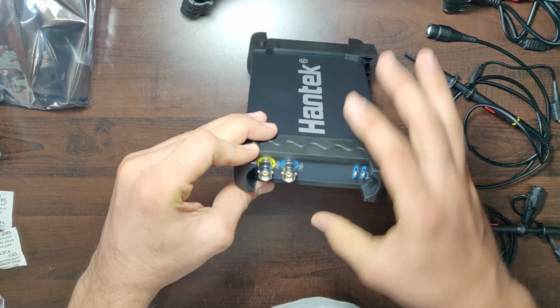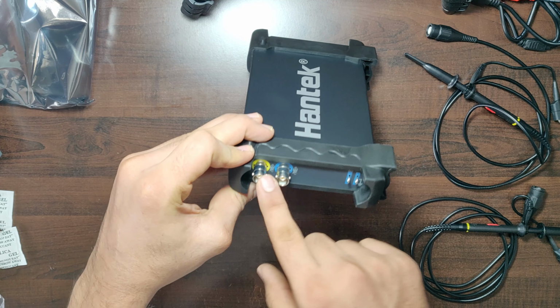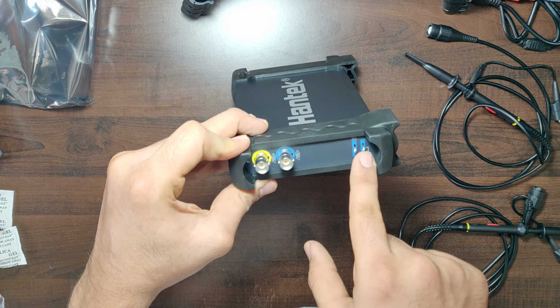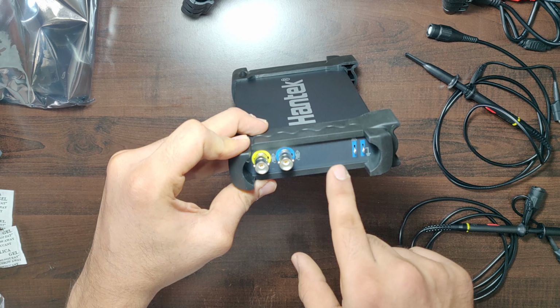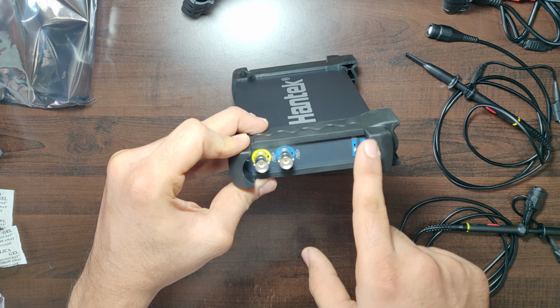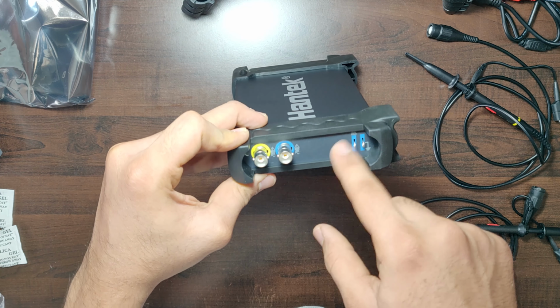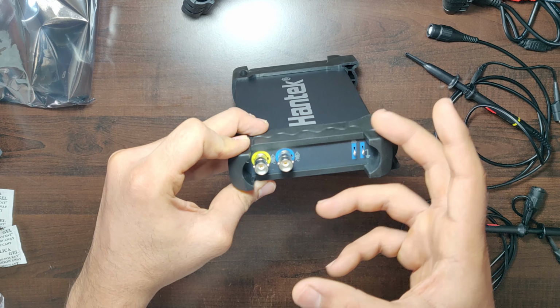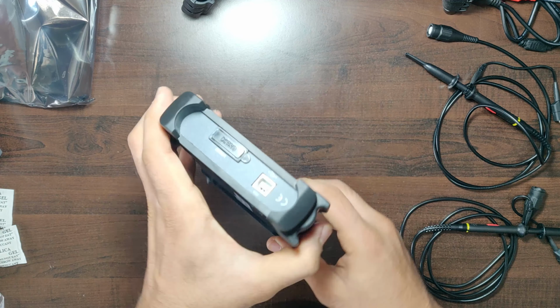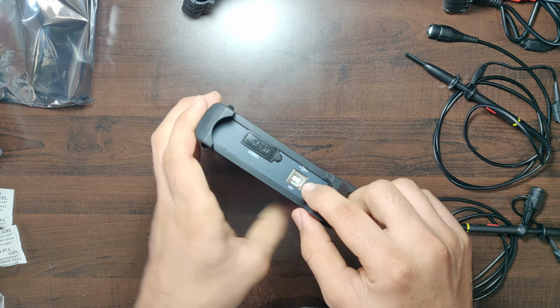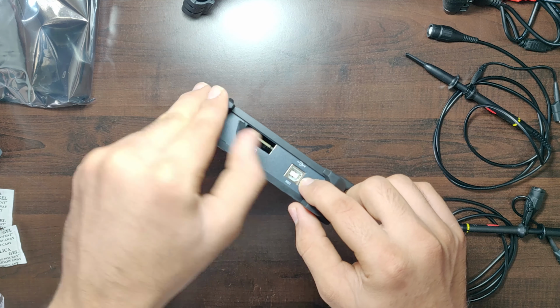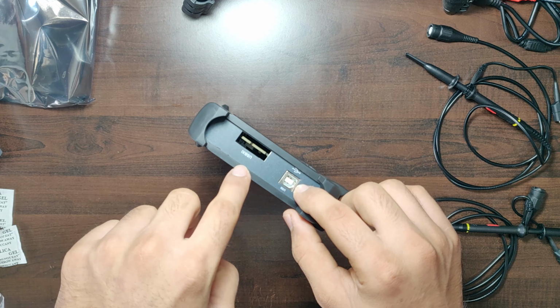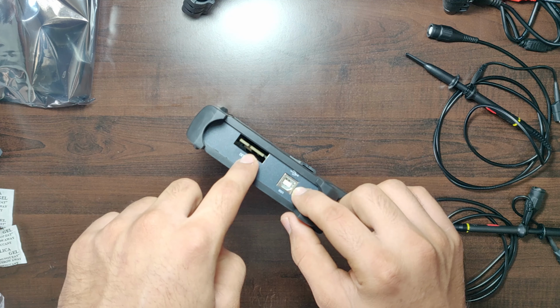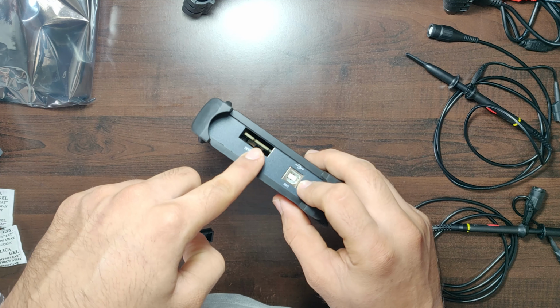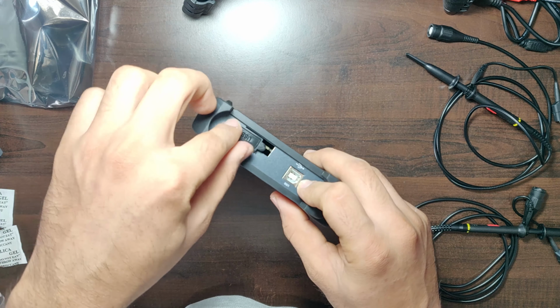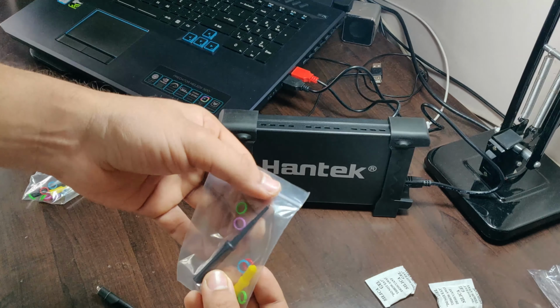Coming into the ports, here you can see the channel 1, channel 2. These are the two ports where you can connect the BNC connectors, and that is a square wave signal generator of 1 kilohertz up to 2 volts, and this is for the calibration of the probes. So on the other side we can see a USB B type connector which connects to the PC, and so this is the mode of the signal transfer, and also this is the power cable for it, and the other port is for the extension for if you want to connect the external devices from HANTEK.